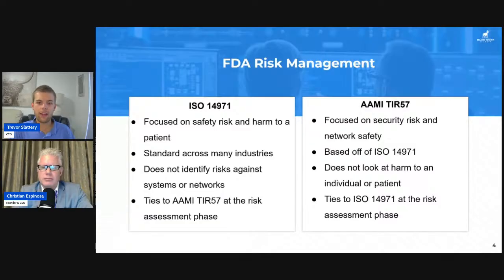Now, this is not just going to be gated to security problems. You may identify during an FMEA exercise that there are certain unacceptable safety risks in the product that have no mapping to security in any way. Similarly, the inverse may be true. And this is when we start talking about AAMI TIR57, and then, as a newer successor that they're starting to work towards, a little bit more of a shift, AAMI SW96. Now, the FDA still talks about AAMI TIR57 as one of the preferred methodologies for going through this process.